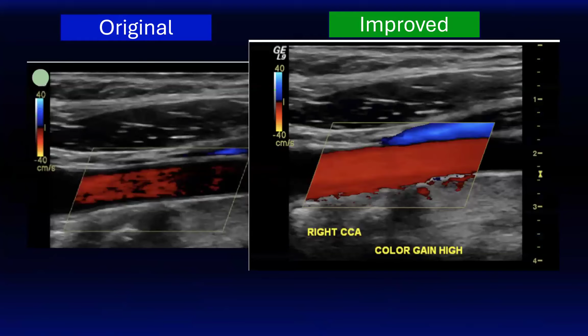On this one, the scale on the left and the right looks the same, but you mentioned something. Can you say what you did there again? This is a little confusing. Absolutely. In the original, there's not a lot of flow showing up. Here's your scale, which is a representation of how the machine is shooting sound waves out. However, just by increasing the gain on the machine, it's only changing how that flow is being displayed on the screen. So your scale is identical, but by increasing the gain, you get a better image of this flow.